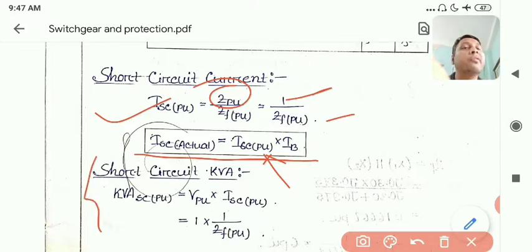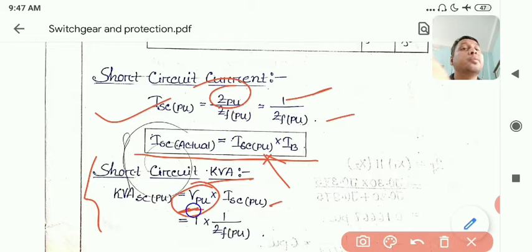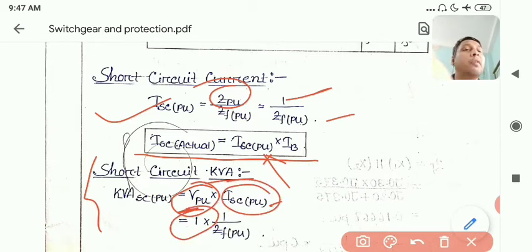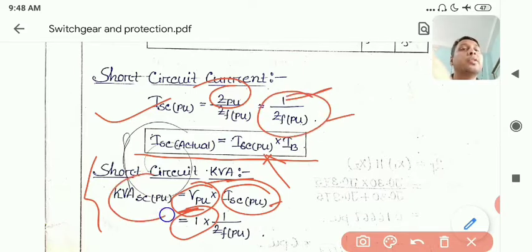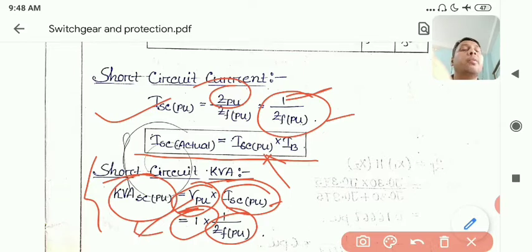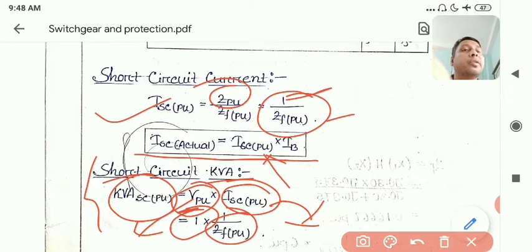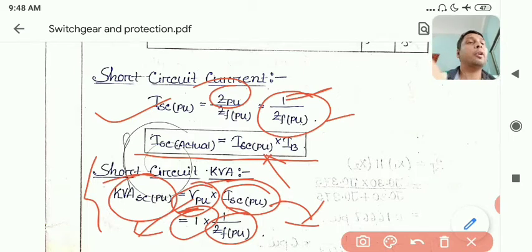For short circuit KVA — from the name itself, KVA requires voltage and current. The voltage is the pre-fault condition voltage, which is 1 per unit, and the short circuit current after the fault is I_sc (pu), which equals 1 divided by Z_f (pu). This product is known as the short circuit KVA. Note that V_pu is the pre-fault voltage at the terminals where the fault is occurring.